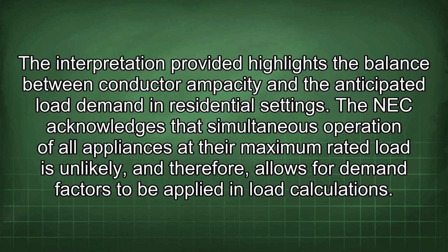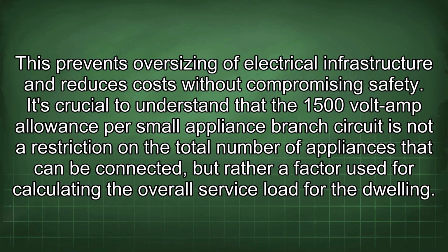The interpretation provided highlights the balance between conductor ampacity and the anticipated load demand in residential settings. The NEC acknowledges that simultaneous operation of all appliances at their maximum rated load is unlikely, and therefore allows for demand factors to be applied in load calculations. This prevents oversizing of electrical infrastructure and reduces costs without compromising safety.